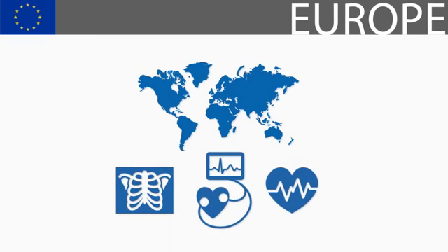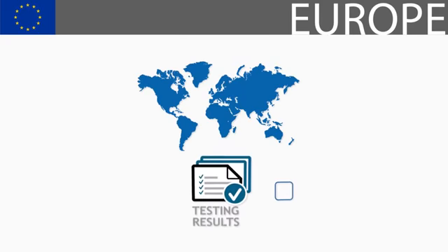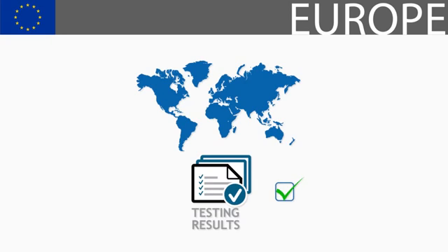If your device requires testing and has been tested to an international standard in another market, those testing reports will generally be accepted as part of your submission to your notified body. However, if there are European harmonized versions, this is the version to which your medical device should be compliant. Many notified bodies perform testing as well.